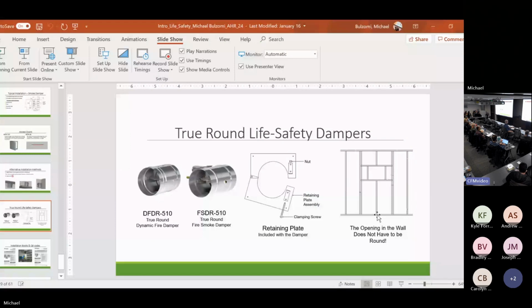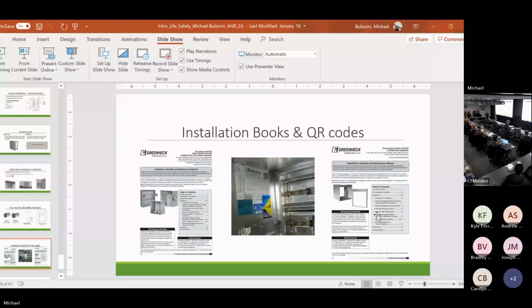I can only get up to 24 inches round. So if I have a larger than 24-inch round, I've got to go to my square with a round transition. But I'm saving money, 20 to 40% more cost effective, cheaper, and up to 85% lower pressure drop. It's a win-win, no brainer. I don't see why anybody would ever want to do otherwise.